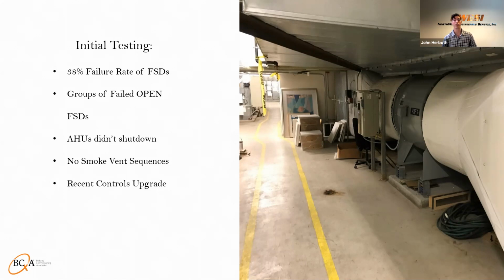And lo and behold, later on, you find out that there was a DDC upgrade, and the DDC was originally the ones shutting down the equipment, or you find out some other scenario where wiring was pulled off of a VFD, and that was supposed to provide the shutdown command. And there was no smoke vent sequences on a floor which had ORs. They were day surgeries, but another scenario where you run into a place that has operating rooms that will shut down all their HVAC equipment if a fire detector gets triggered anywhere on that floor.